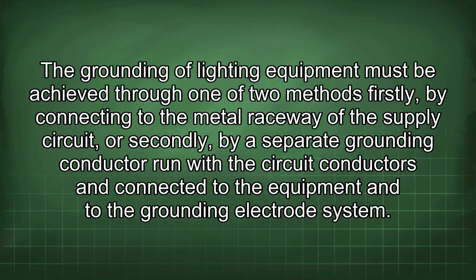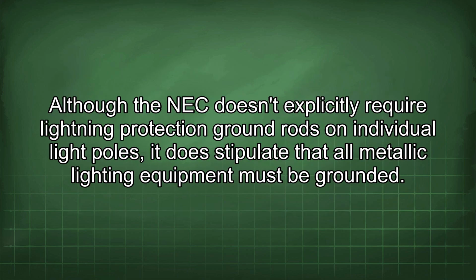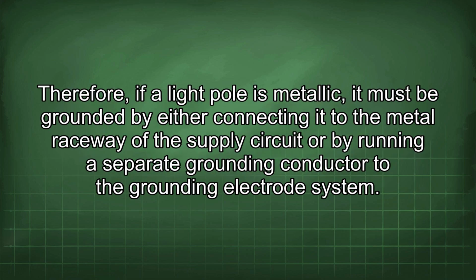The grounding of lighting equipment must be achieved through one of two methods: firstly, by connecting to the metal raceway of the supply circuit, or secondly, by a separate grounding conductor run with the circuit conductors and connected to the equipment and to the grounding electrode system. Although the NEC doesn't explicitly require lightning protection ground rods on individual light poles, it does stipulate that all metallic lighting equipment must be grounded. Therefore, if a light pole is metallic, it must be grounded by either connecting it to the metal raceway of the supply circuit or by running a separate grounding conductor to the grounding electrode system.